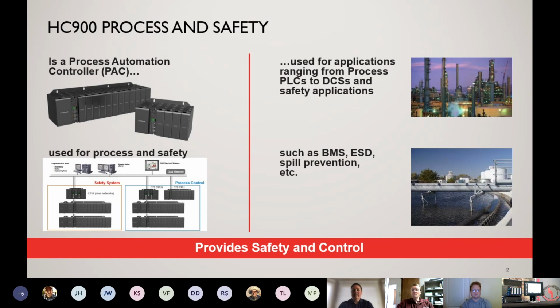So if you did have an application that had both, you can use the same processor for both applications. Or if you had a situation where you needed to separate that, you can have a dedicated rack for process and a dedicated rack with its individual CPU for safety. We've used the HC900, safety HC900, for a lot of burner management type systems.